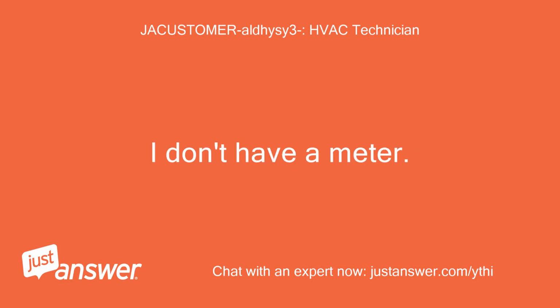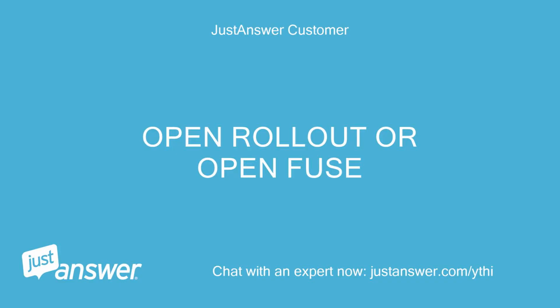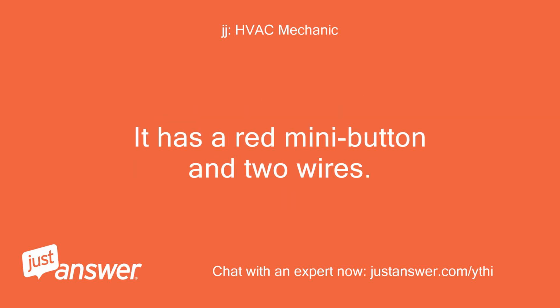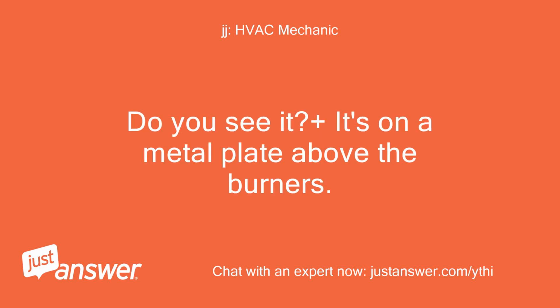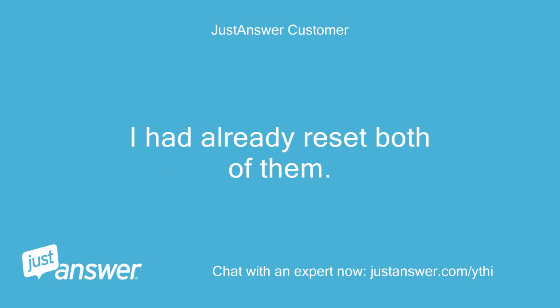I don't have a meter. Is there printing on the inside panel that tells what the flashing 6 indicates? Open ROLLOUT or open fuse. A ROLLOUT switch is a manual reset switch on most of those Goodman units. It has a red mini button and 2 wires. Do you see it? It's on a metal plate above the burners. Yes, it has 2 of them. I had already reset both of them. No help.